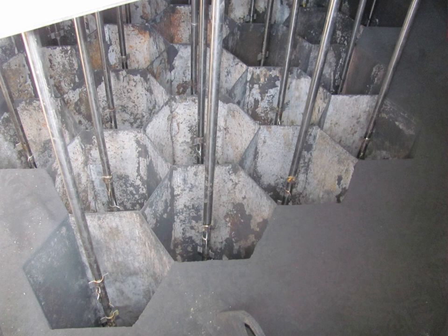The presence of SO3 in the gas stream has been shown to favor the electrostatic precipitation process when problems with high resistivity occur. Most of the sulfur content in the coal burned for combustion sources converts to SO2. However, approximately 1% of the sulfur converts to SO3. The amount of SO3 in the flue gas normally increases with increasing sulfur content of the coal. The resistivity of the particles decreases as the sulfur content of the coal increases. Other conditioning agents, such as sulfuric acid, ammonia, sodium chloride, and soda ash, sometimes as raw trona, have also been used to reduce particle resistivity. Therefore, the chemical composition of the flue gas stream is important with regard to the resistivity of the particles to be collected in the ESP. The table below lists various conditioning agents and their mechanisms of operation.